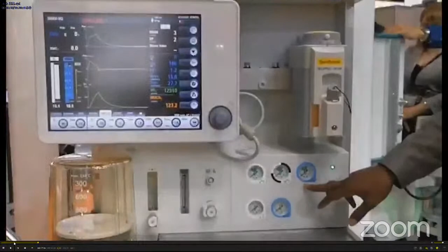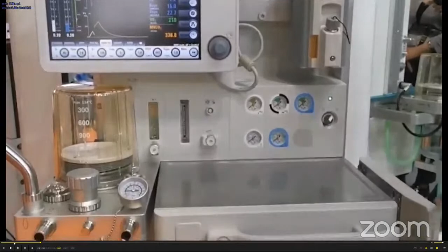Here we have our pressure gauge for air, oxygen and N2O for central gas and N2O. Here we have our auto flush. With 3 drawers, we have two positions of vaporizer. This machine has an electronic flow meter to control the flow of air, oxygen, and N2O. Also, it has a backup mechanical flow meter.